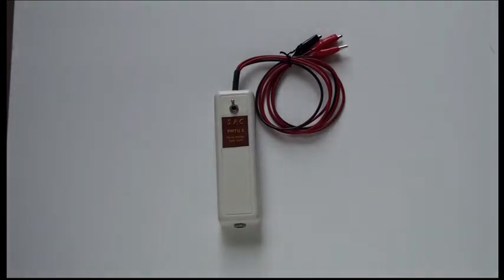The power socket can accept any voltage between 12 and 24 volts AC or DC from a transformer type power supply, and it is not polarity conscious when used with DC. Don't use a switching type power supply - they don't charge the unit properly and the results of testing can't be relied on.